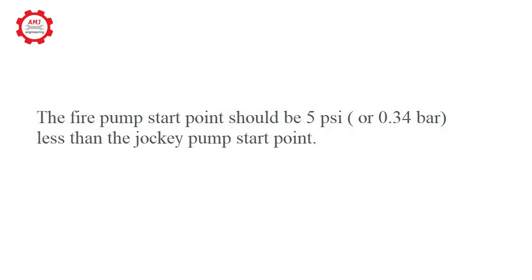For the main pump, NFPA 20 states the following: The fire pump start point should be 5 psi, or 0.34 bar, less than the jockey pump start point.